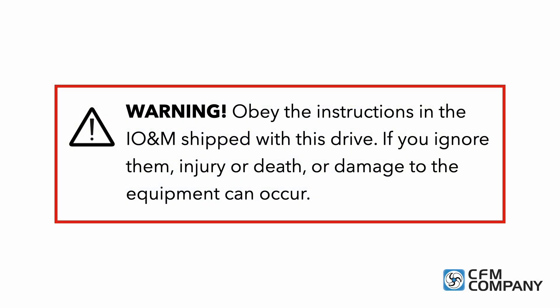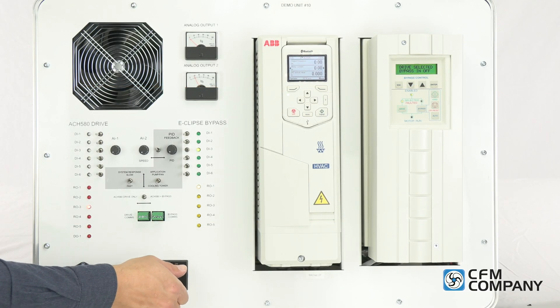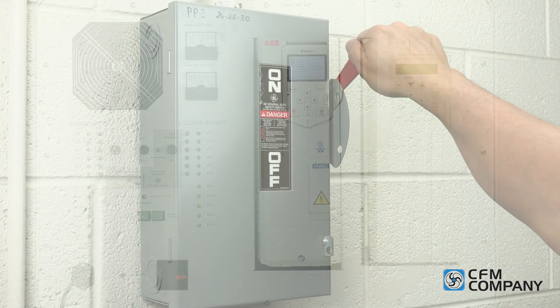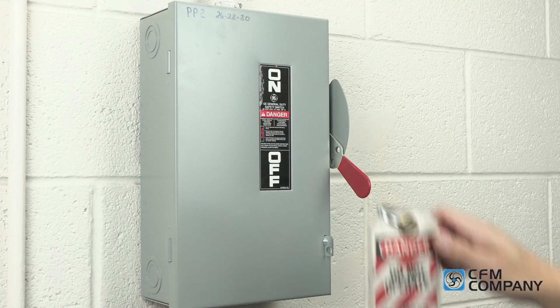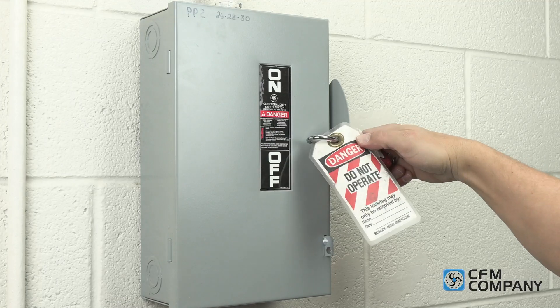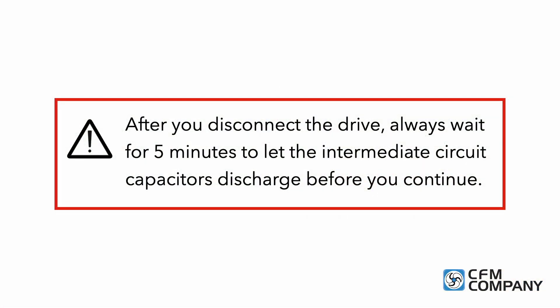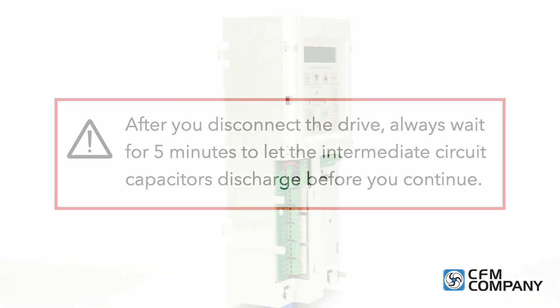Obey the instructions provided in the IO&M shipped with this drive. If you ignore them, injury or death or damage to the equipment can occur. Before removing the front cover of the ABB ACH 580, disconnect the power to the drive. Lock out and tag out the circuit disconnect and make sure that reconnection is not possible. Always wait five minutes to let the intermediate circuit capacitors discharge before you continue.